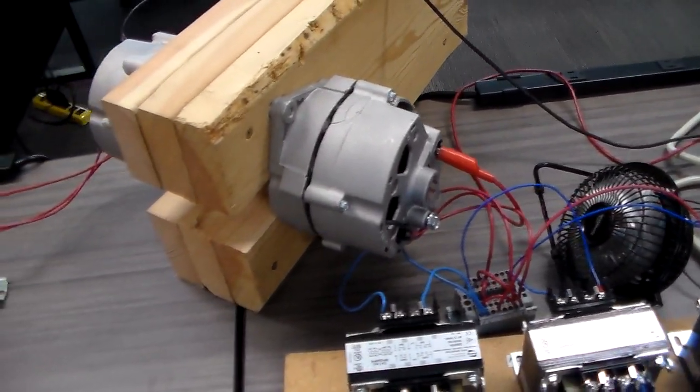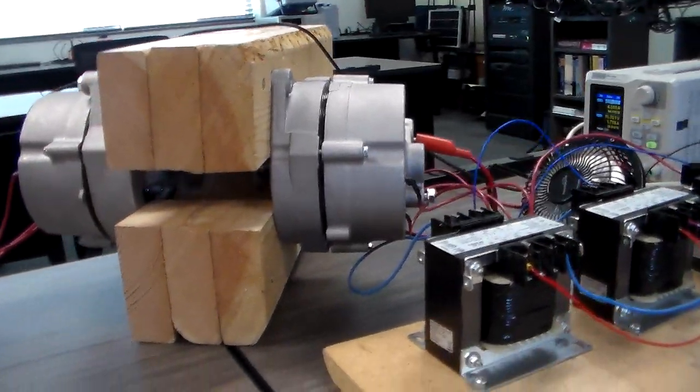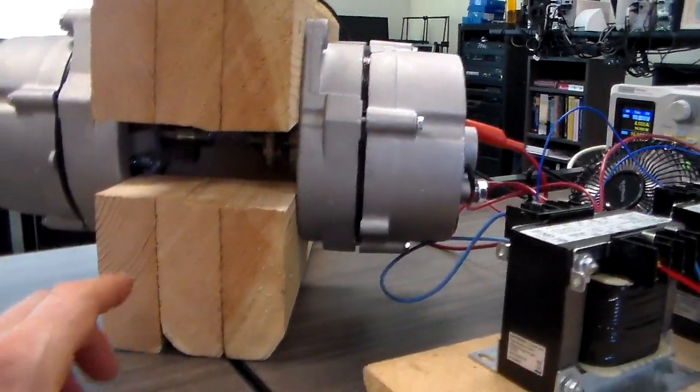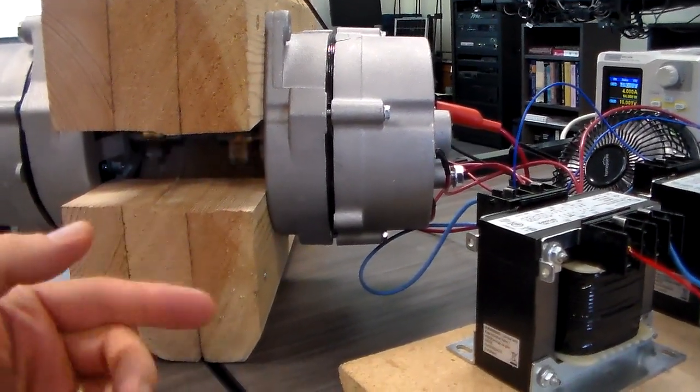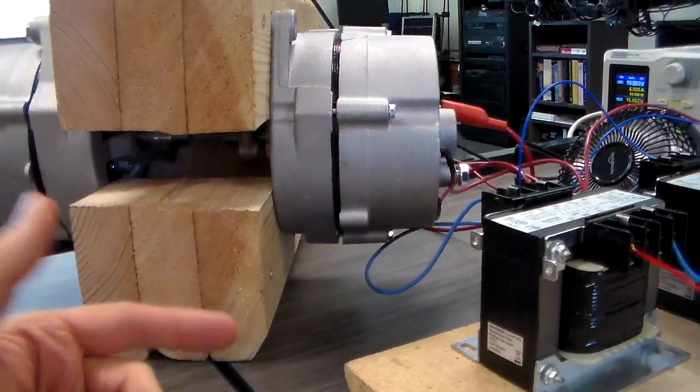Because we're spinning this very slow at 60 Hz, these being 14-pole machines, we're only spinning at about 514 RPM, so the amount of cooling they get from their normal centrifugal fans is pretty minimal.